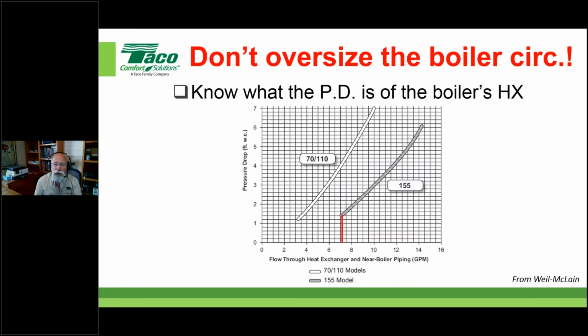Those numbers I just showed you are referencing flow through the heat exchanger based on GPM. Notice this is a little over 7, and at a little over 7, you're only going to have a 1.5 foot pressure drop, okay? That's relatively really low, but what delta T is that? Anybody want to guess? For the sake of time, I'm going to go ahead and throw it out there. Okay. So I'm just going to do a ladder here, right? I'm going to show you what it looks like at a 30. I'm going to show you what it looks like at a 20. Okay. Again, nice round numbers here. I mean, if somebody wanted to do a 25, you could extrapolate and come up with a GPM on that.